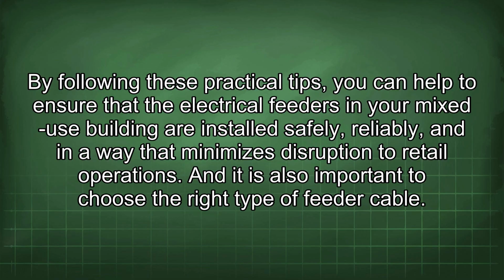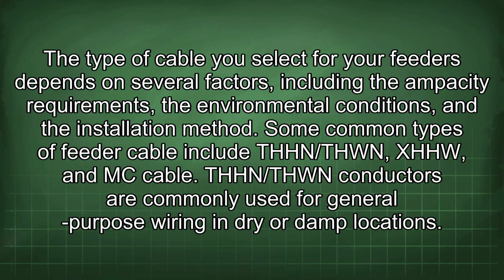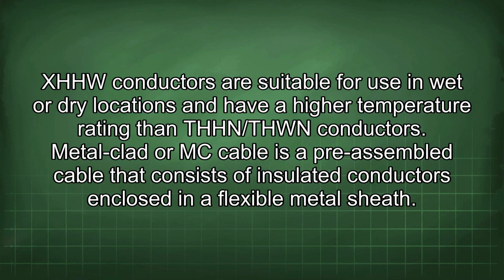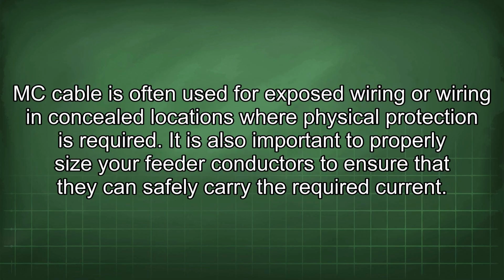And it is also important to choose the right type of feeder cable. The type of cable you select for your feeders depends on several factors, including the ampacity requirements, the environmental conditions, and the installation method. Some common types of feeder cable include THHN/THWN, XHHW, and MC cable. THHN/THWN conductors are commonly used for general-purpose wiring in dry or damp locations. XHHW conductors are suitable for use in wet or dry locations and have a higher temperature rating than THHN/THWN conductors. Metal-clad or MC cable is a pre-assembled cable that consists of insulated conductors enclosed in a flexible metal sheath. MC cable is often used for exposed wiring or wiring in concealed locations where physical protection is required.